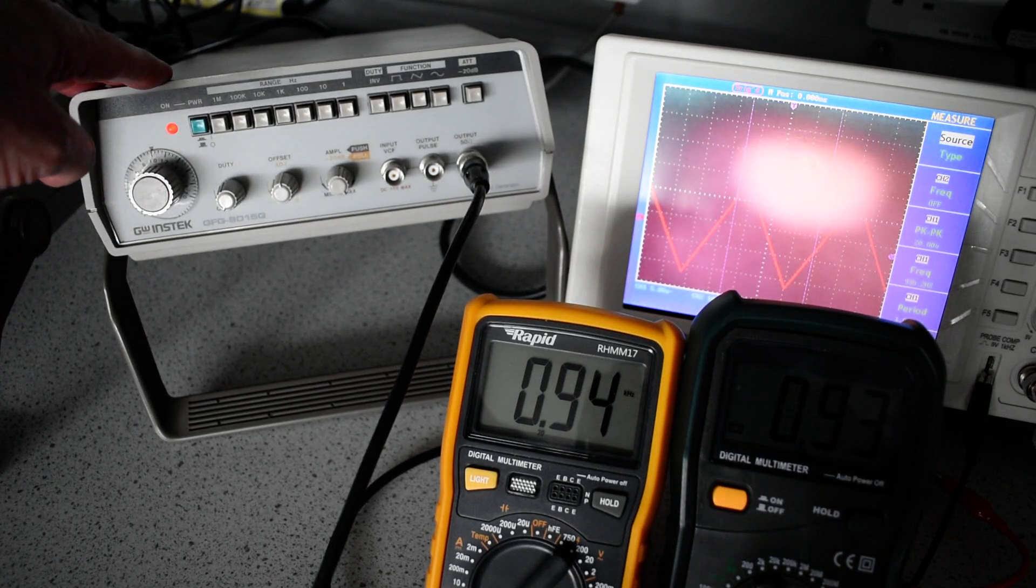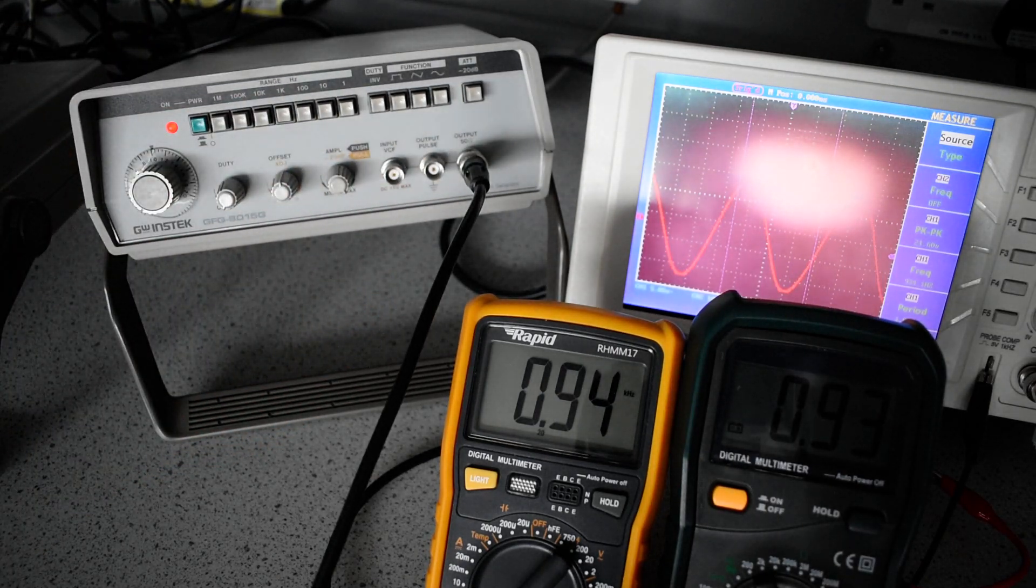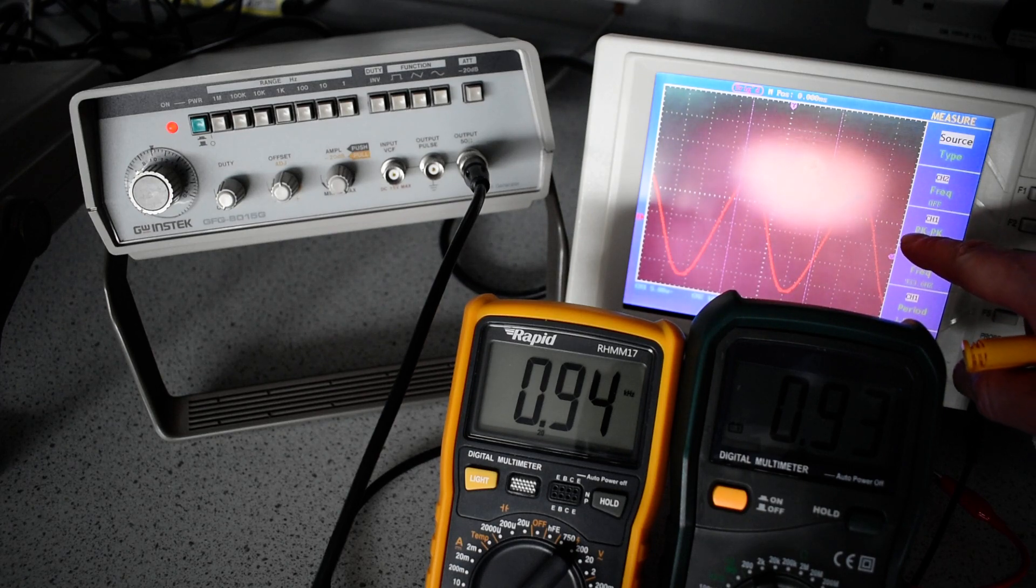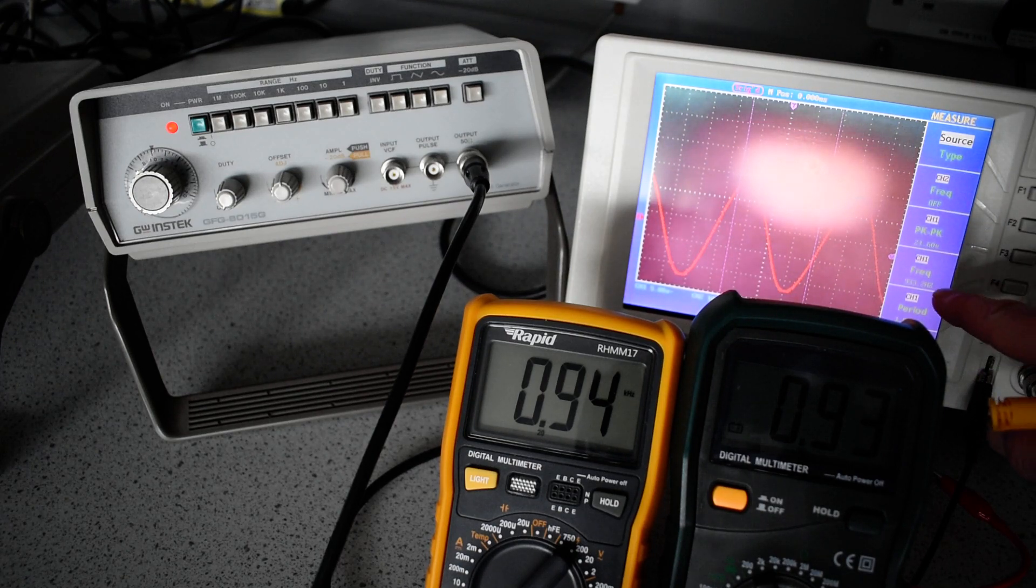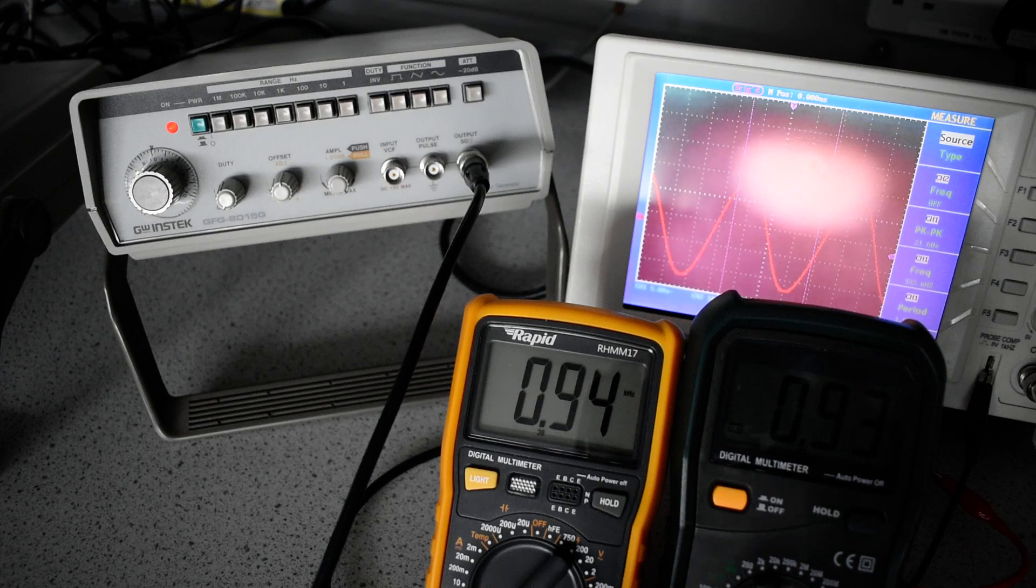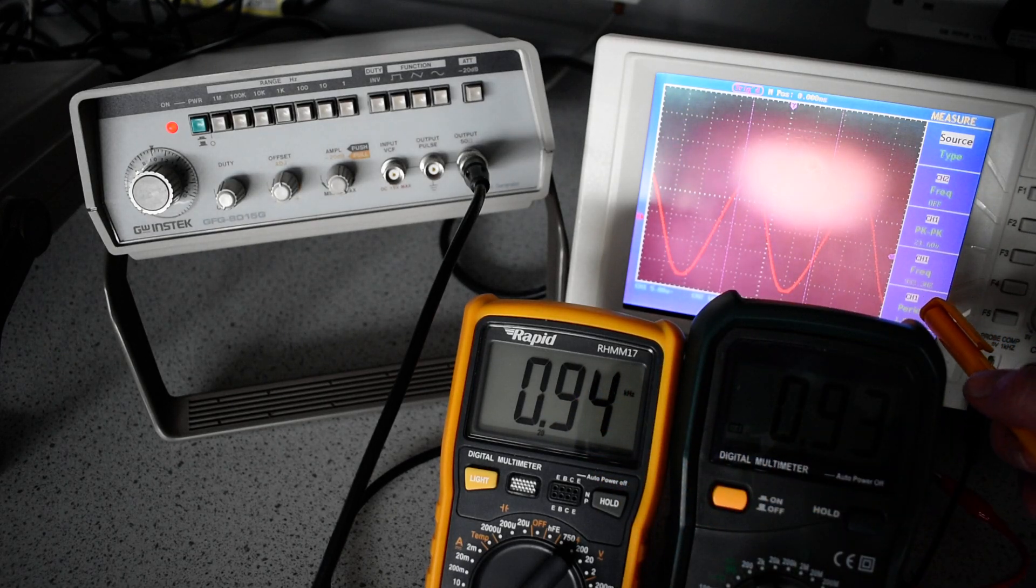If we change to a sine wave, again, we get our peak to peak greater than 20 volts, 21.6, so that's within spec. However, the frequency output does appear to be outside spec below 950. We're reading consistently 940 hertz, so it's outside specification.